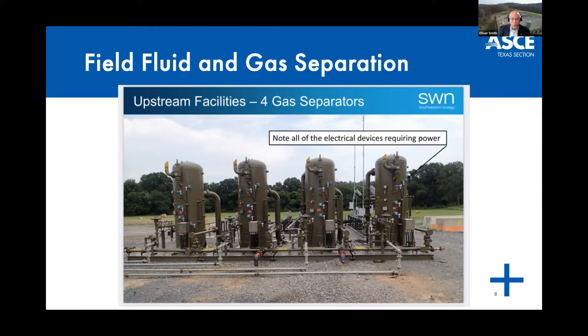Well, it tells you that there are numerous valves that are instigating a pressure drop in the system, and that pressure drop across the valves facilitates the formation of hydrates, which crystallize when ambient temperatures drop below 40 degrees for sustained periods of time, as I alluded to earlier. Interruption of the supply of electricity to the wellhead and separators automatically causes the well production operation to shut in to prevent loss of control of the fluid and gas production and subsequent pollution of the surrounding environment.